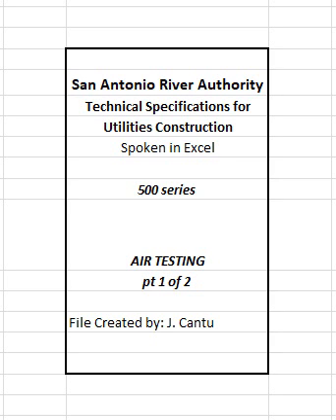Backfilling to grade shall be completed and all laterals, stubs, and openings shall be capped or plugged by the contractor before the test. Manholes are to be plugged so they are isolated from the pipe and cannot be included in the test. Under no circumstances is one section of pipe or material, i.e. ductile iron pipe, to be tested with another pipe section or material, i.e. PVC pipe, at the same time.